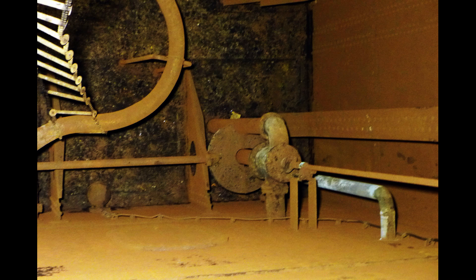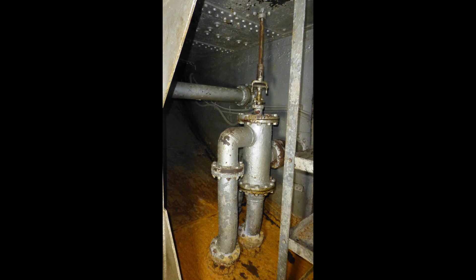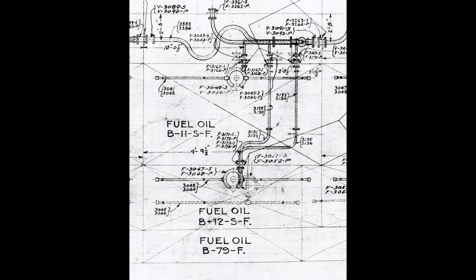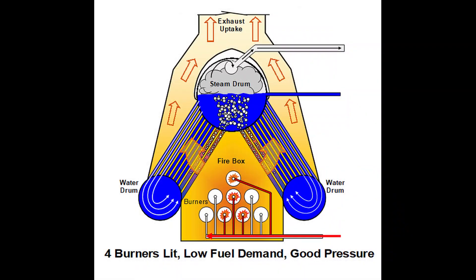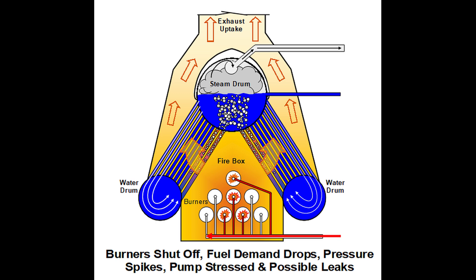The low pickup is typically 2 to 10 inches off the bottom and the high 12 to 18 inches. A photo of one mounted just above a fuel tank in the double bottom shows the separate inputs and a feed line coming out the other side. Here's where we literally double the pipes and valves required in the fuel system by installing recirculate pipes and valves to all tanks. Fuel feed lines can provide fuel to the boiler rooms by themselves, but flow and pressure are impossible to regulate. Sudden increases in steaming rate mean slow-turning booster pumps must greatly increase their output and fuel pressure drops until they catch up. Likewise, closing burners suddenly decreases fuel flow, causing pressure spikes that force relief valves open and stress pumps and pipe joints.